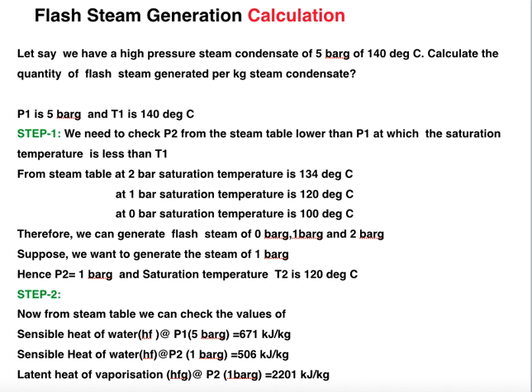Now let's work through a flash steam generation calculation example. We have high pressure steam condensate at 5 bar gauge and 140°C. Calculate the quantity of flash steam generated per kg of steam condensate. Here P1 is 5 bar gauge and T1 is 140°C. In step 1, we check P2 from the steam table — a pressure lower than P1 at which the saturation temperature is less than T1.